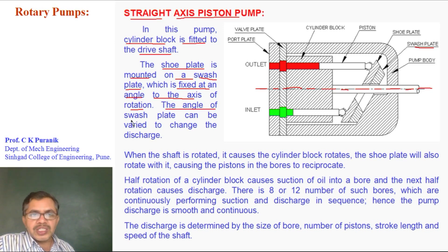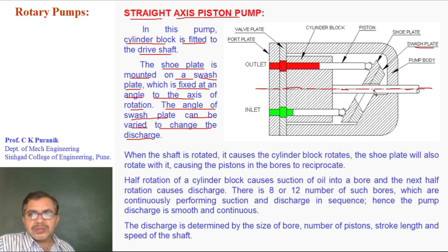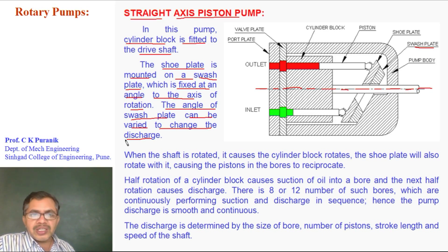The angle of the swash plate can be varied in order to change the discharge. There is a mechanism to change the angle of the swash plate, though that mechanism is not shown in this figure. By changing this angle of the swash plate, we can change the rate of flow of oil — that is, the discharge of the pump.